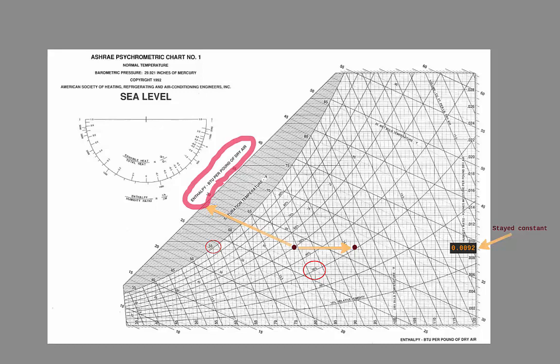But you might be wondering, isn't there a dependence on pressure as well? Yes, there is. The psychrometric chart shown here is only for sea level pressure. Some of the more sophisticated sensors, like the ones used to calibrate other sensors, would include a pressure measurement to ensure the reported value of enthalpy was as accurate as possible. But for typical HVAC processes, the level of accuracy is not warranted, thus a constant pressure is assumed, whether that be sea level pressure or some other atmospheric pressure associated with the elevation of the location you are installing such a sensor.